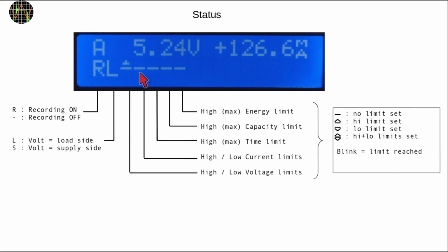In this case, there's only a high voltage limit enabled. Every measurement is continuously checked against all enabled limits, and if any one is exceeded, the relay deactivates and the corresponding status symbol blinks. If the value goes back into the limit, the symbol stops blinking, but the relay will stay deactivated until it's manually rearmed.